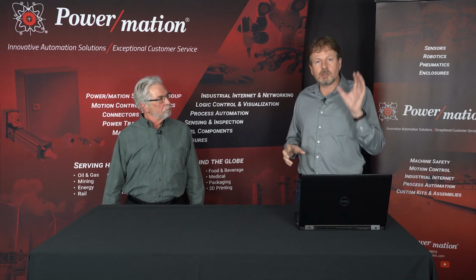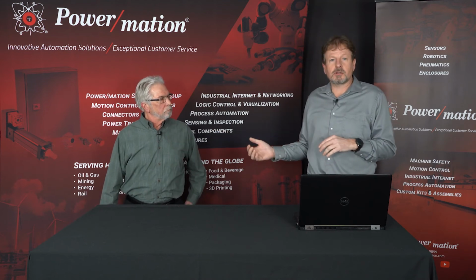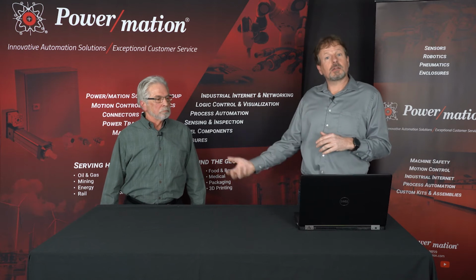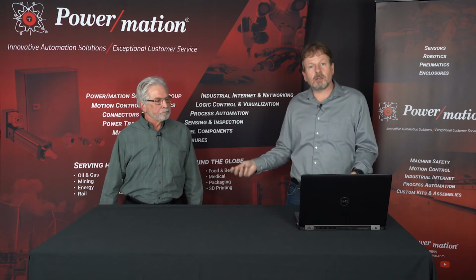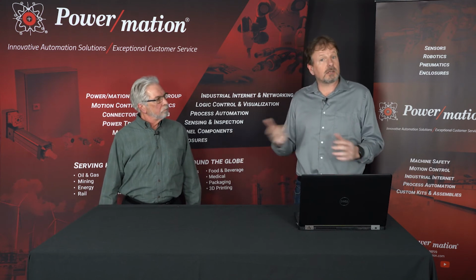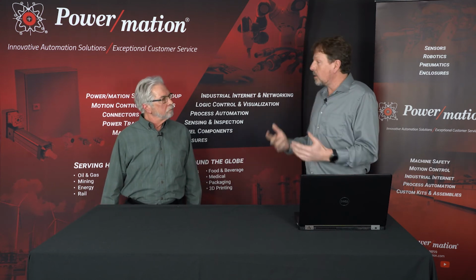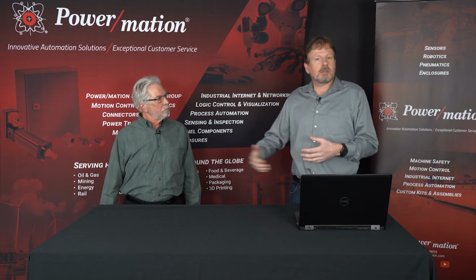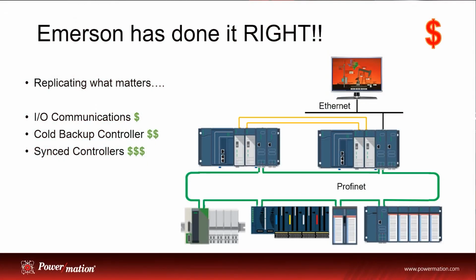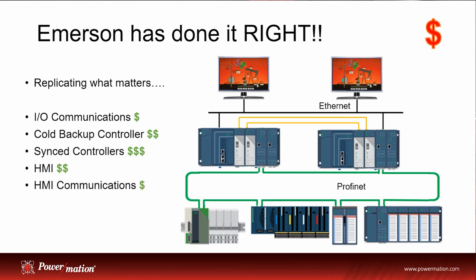You've got a primary that's doing all the heavy lifting, and you've got a secondary coming in when the primary starts coughing, and the secondary takes over, controls the I/O, right? Correct. The secondary comes back on, or the secondary recognizes the primary came back online, primary takes back over again, and the secondary can gracefully walk away. So in this case, we talk about redundancy, what's referred to as a warm standby, where you have a CPU that's there ready to go. Yep. It can be synchronized, but maybe not as a super high speed thing.